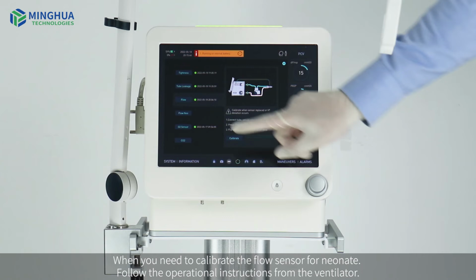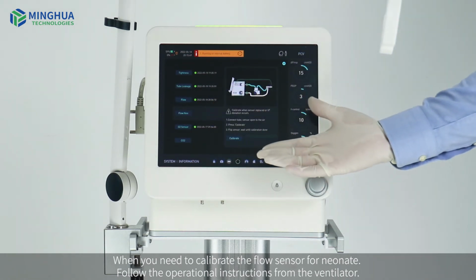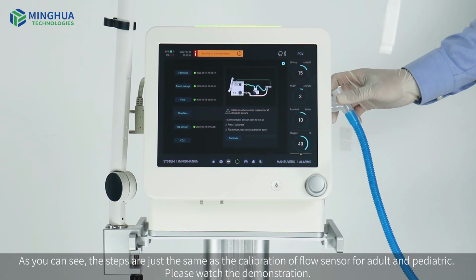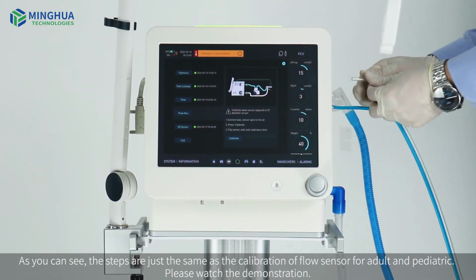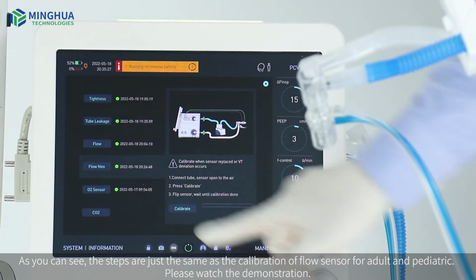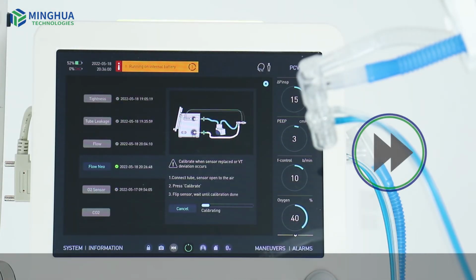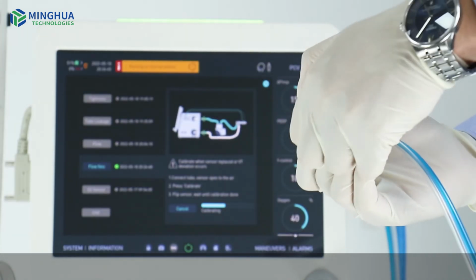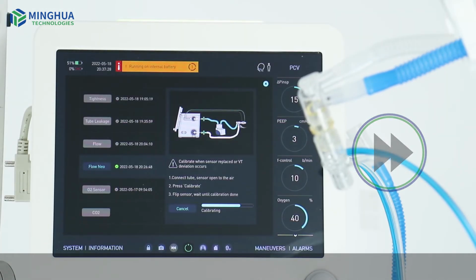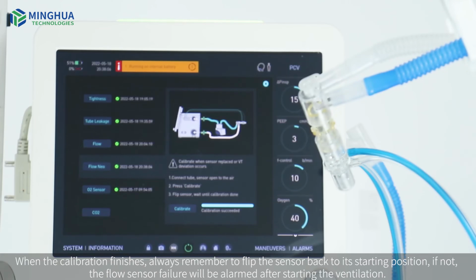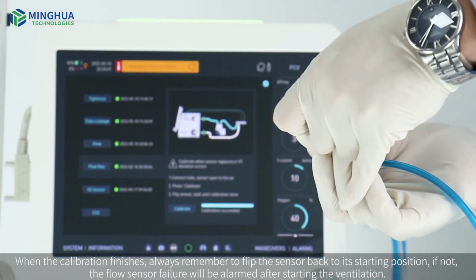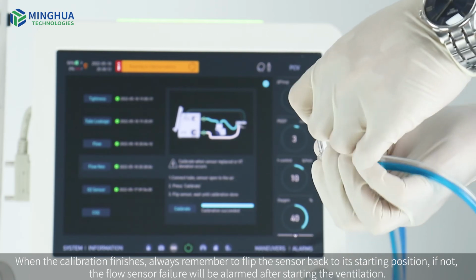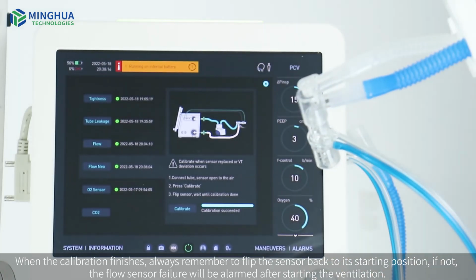When you need to calibrate the flow sensor for neonate, follow the operational instructions from the ventilator. As you can see, the steps are just the same as the calibration of flow sensor for adult and pediatric. Please watch the demonstration. When the calibration finishes, always remember to flip the sensor back to its starting position. If not, the flow sensor failure will be alarmed after starting the ventilation.